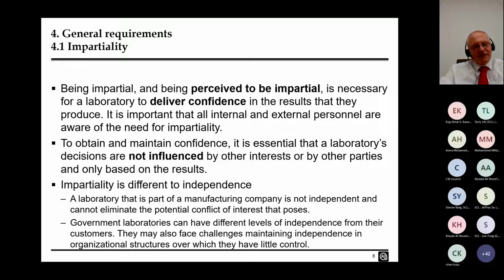We're not saying you have to be independent. You can be a laboratory that's part of a manufacturing company. You can be a government laboratory working for other sections of government. We're not looking for independence. We're looking at impartiality. Those structural relationships with your company or your government should not be affecting the results that you produce on your certificates.